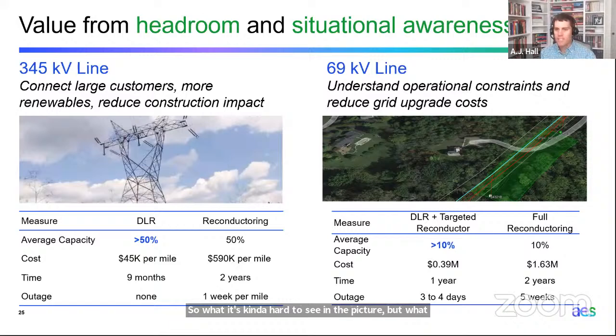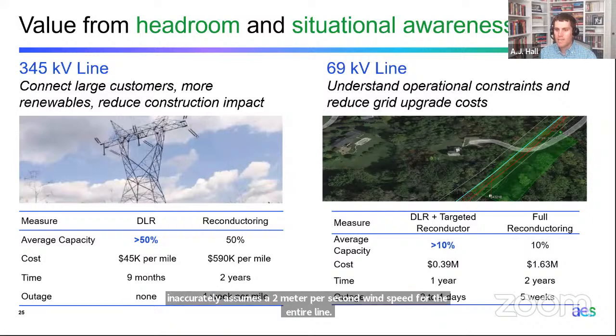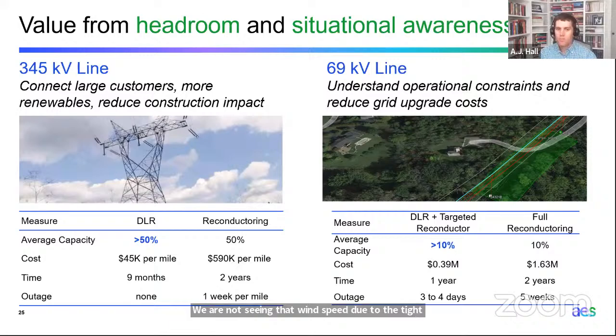It's running through a very tight vegetation corridor. Currently, our static rating on the line inaccurately assumes a 2 meter per second wind speed for the entire line. However, we are not seeing that wind speed due to the tight vegetation in this corridor. So to increase the capacity of this line and maintain its existing rating, we could just fully reconductor the line, which would be the traditional solution at a cost of $1.63 million.